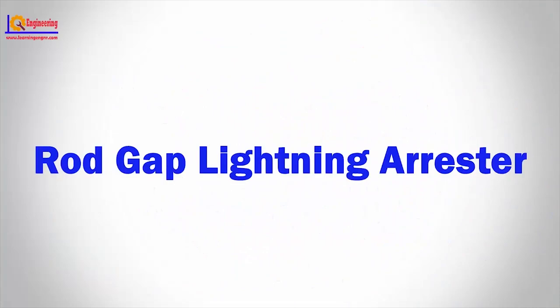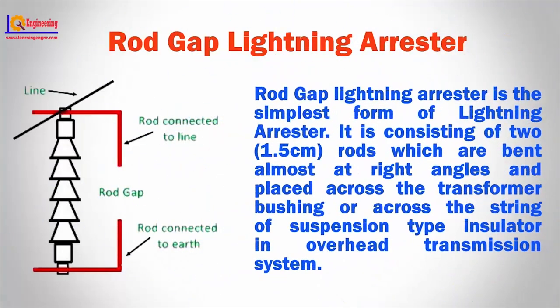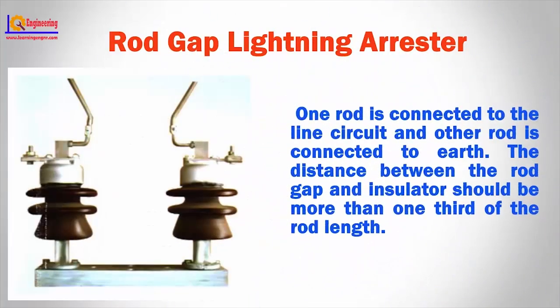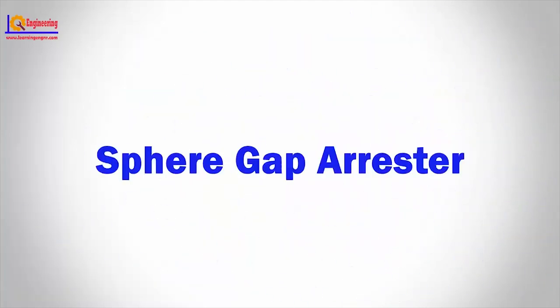Rod gap lightning arrester is the simplest form of lightning arrester. It consists of two rods which are bent almost at right angles and placed across the transformer bushing or across the string of suspension type insulator in overhead transmission system. One rod is connected to the line circuit and the other rod is connected to earth. The distance between the rod gap and insulator should be more than one-third of the rod length.